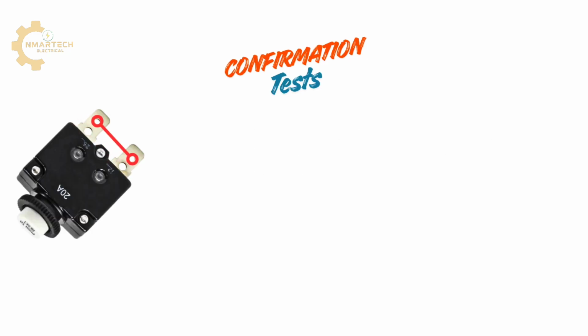Now, there is one last important test, very important. Simply bypass the breaker just by shorting the terminals. After that, start your generator with no load. Then after some minutes, add a little load and observe. If your gen runs smoothly, just install a new breaker and that's it. But if your generator vibrates aggressively, struggles or sounds overloaded, please switch off immediately. This indicates that the breaker has been protecting a deeper fault. We'll get to that later.